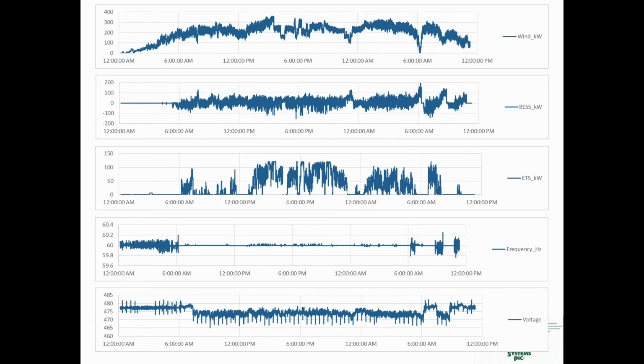On the second last graph, we can see the frequency, and we notice that the BESS does a better job of balancing frequency than the diesels do, which makes sense. The diesels have to balance frequency by mechanically throttling back and forth on the fuel they're putting into the system. The BESS can do it much more quickly.